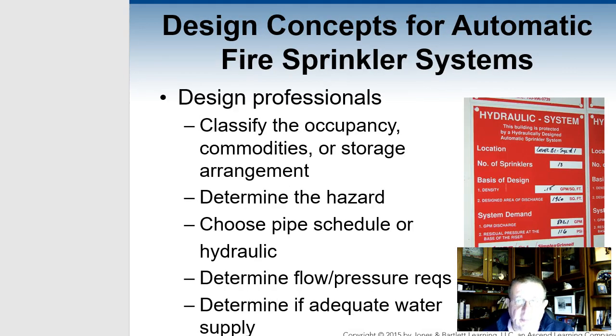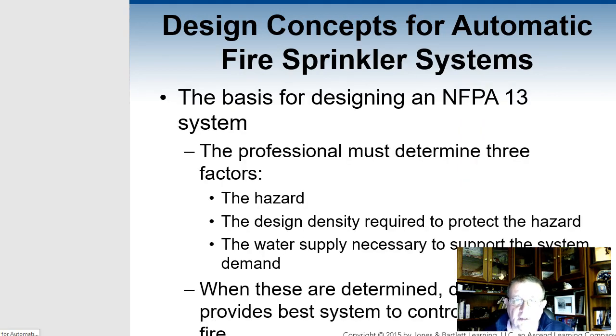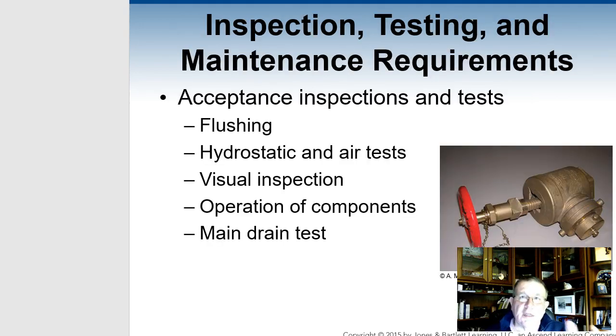The big thing is how the system's classified. You'll see the hydraulic system chart on the system. It'll tell you exactly what it is, what it's been tested for, and what's the density and the square footage that it's going to cover. In this particular slide, you see that 1950 is the square footage that it's going to discharge out to. So it gives you a good idea. One of the big things is you start looking at what is the hazard, what is the density, and what is the supply of water needed to make the sprinkler system work. This is where you have to look at the calculations, and a fire protection engineer needs to say that, along with, guess what, the building engineer, the person that's going to engineer the building.